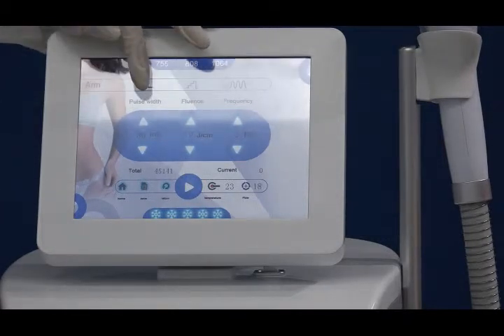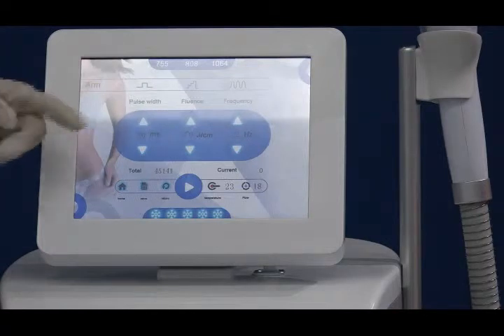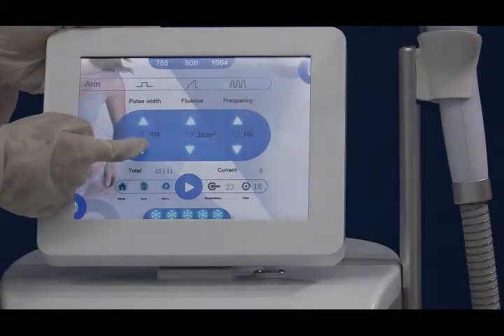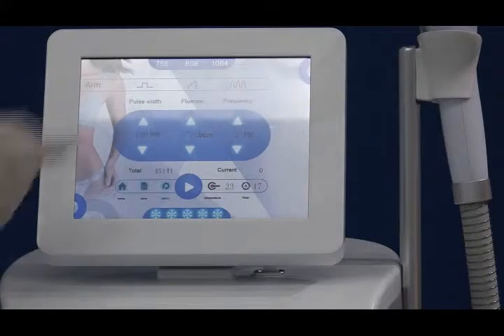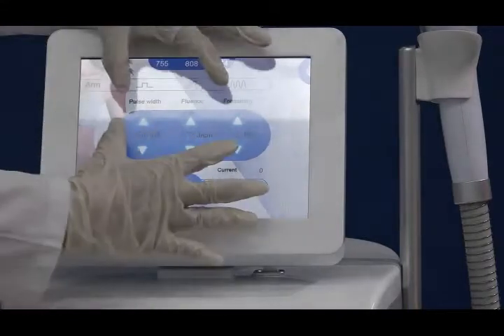You can adjust the energy according to client's cooling, okay? Client feel a little bit painful and a little bit warm, it's okay. This is fluence. And this is pulse width. Pulse-wise means one laser, one shot laser treatment time on the skin, okay? This one. You can adjust here. From five milliseconds to 150 milliseconds. And the pulse width adjustment also related with the frequency, okay?